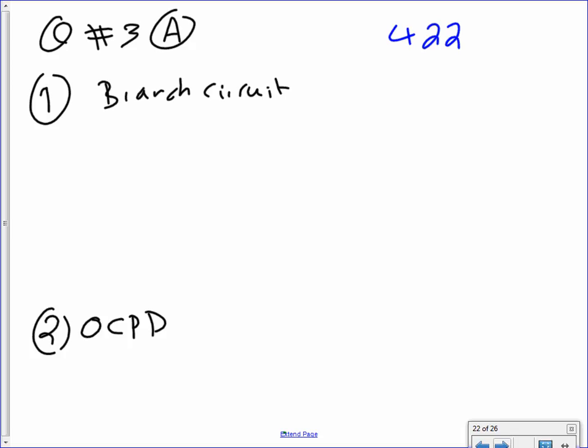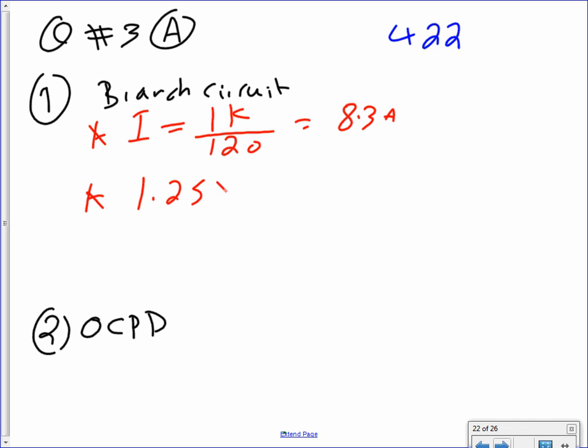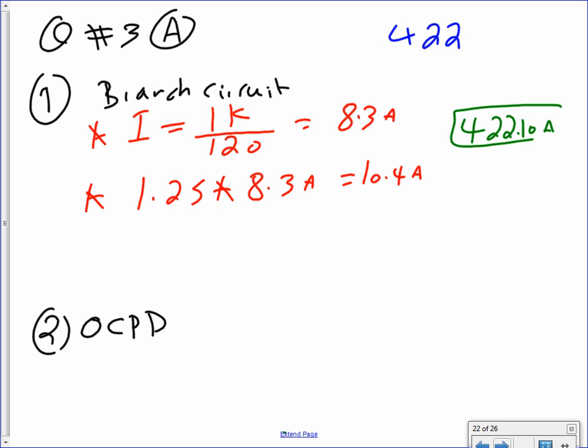So let's go ahead and size the first thing. Let's start with the branch circuit for my garbage disposal. The first thing you need to do is find the amps. It's a 1 kW load, 1K divided by 120. So 1000 divided by 120 gives me 8.3 amps. Then it's a continuous load, 1.25 multiplied by 8.3 amps, and that will get you 10.4 amps. The reference for this is 422.10, that's a continuous load.